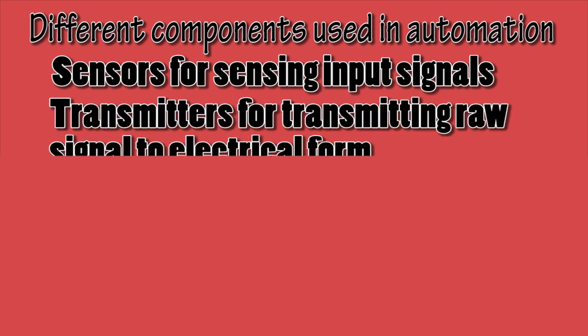Transmitters are used for transmitting raw signals into electrical form. Transmitters convert the raw signal to usable signals such as 4 to 20 mA, 0 to 10V DC, or 0 to 5V DC. There are three types of transmitters: two-wire, three-wire, or four-wire transmitters.